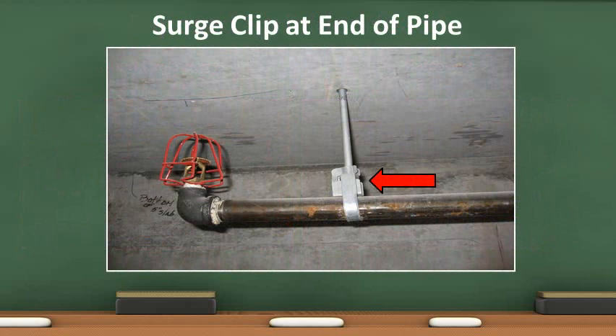When sprinkler heads fuse, the water inside is under tremendous pressure and can cause the piping to rotate when there is space between the branch line and the bracing. Surge clips are installed to hold the pipe in place.